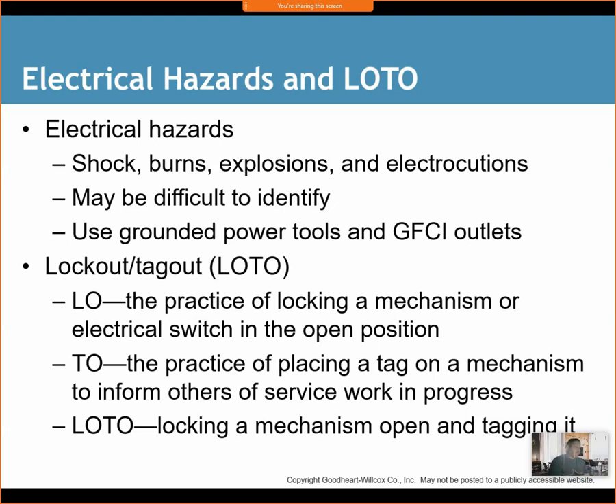When we're talking about being safe around electrical and mechanical equipment, there's a system in place called lockout tagout. The whole practice is to lock out a mechanism or electrical switch in the open position, meaning whatever we're working on isn't going to get power. The reason we want this is in case I turn off a switch and go work on a machine, somebody can't come behind me and turn that switch back on. If that happens, I may get electrocuted, get my arm trapped, or even potentially die depending on the machinery I'm working on.